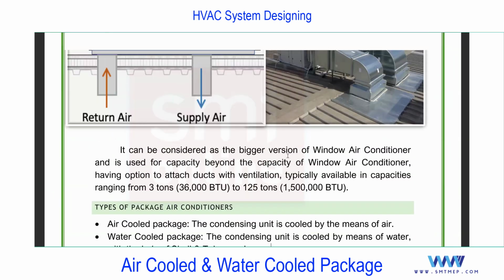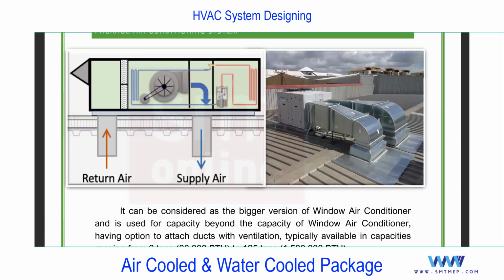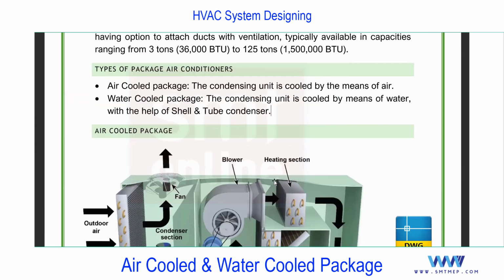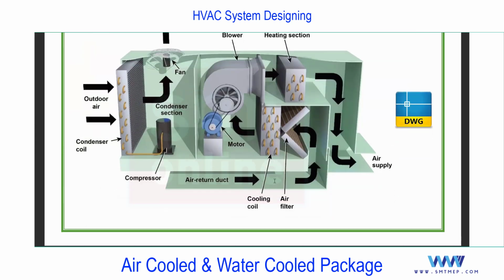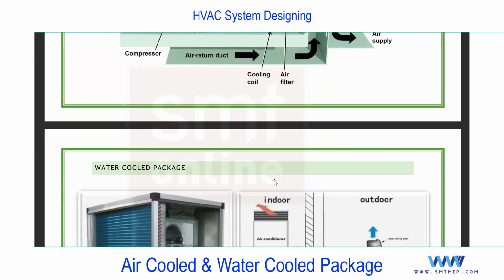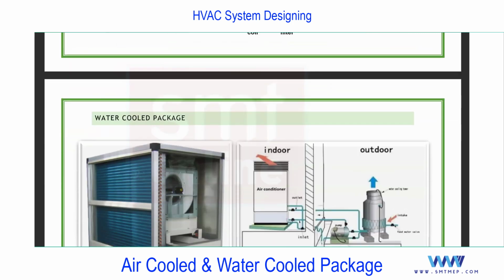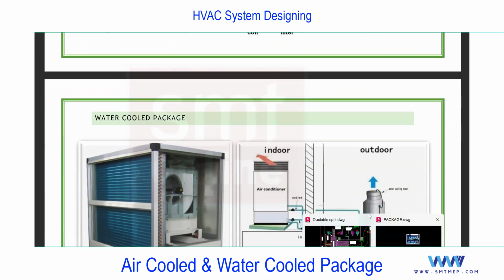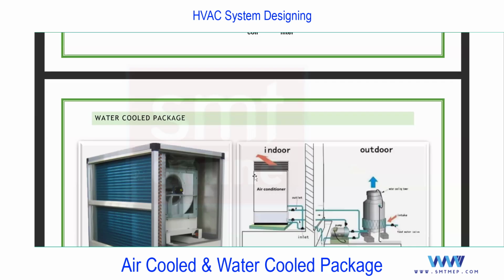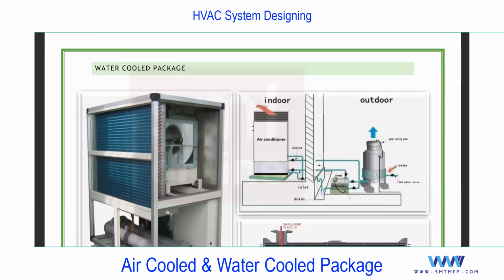So why are we calling it air-cooled? Because, you know, the condensing unit. Now we'll talk about the water-cooled package. You see, in the water-cooled package, this side is 100% same. Means this air side, this supply duct, this side is 100% same in the water-cooled package. You'll find the change in the condensing side. So in the water-cooled package, the condensing unit is cooled by water.